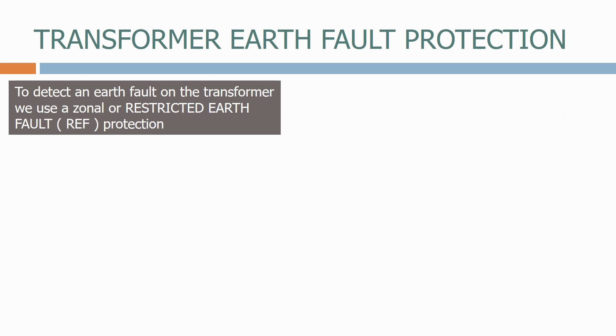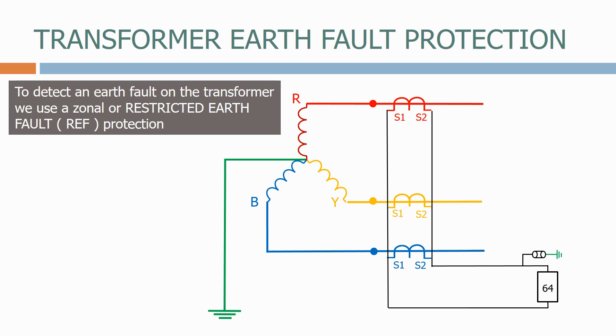To detect an earth fault on the transformer, we use a zonal, or restricted earth fault protection. To make it zonal, we connect the three phase CTs to a CT on the ground connection.